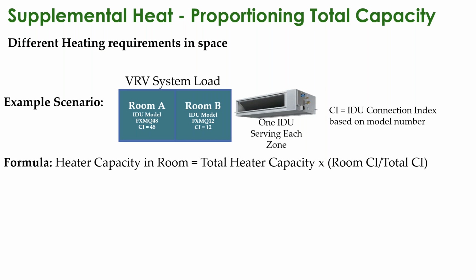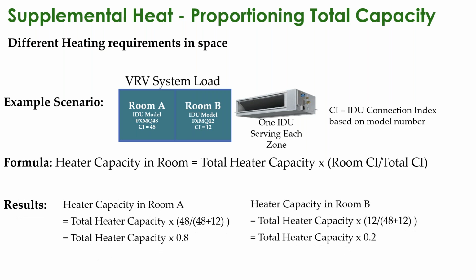The nominal capacity in room A is 48,000 BTUs, and the nominal capacity in room B is 12,000 BTUs, and the connection index is the same based off of the model number. So the formula to calculate the heater capacity in each of those rooms is the total heater capacity times the room connection index divided by the total connection index. When running that, the heater in room A would be 80% of your total heat, and the heater in room B would be 20% of your total heat.